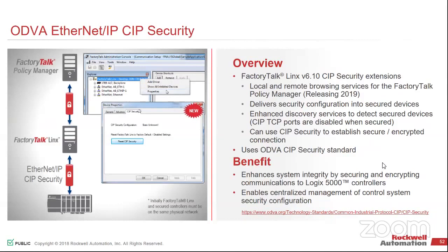This diagram on the left really shows a couple different levels of management. FactoryTalk Policy Manager will be your architecture-level security overview management tool with regards to the Rockwell hardware. CIP security will be the actual protocol on the wire itself. Configuring which devices have secured communications to which devices with CIP security will be performed in FactoryTalk Policy Manager. In about 2 or 3 months, we're going to do user groups specifically on CIP security, or what we're doing for CIP security.